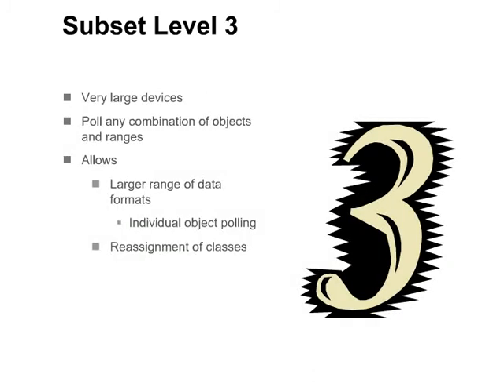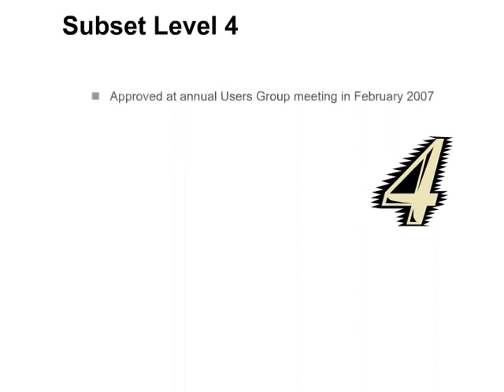Subset level 3 is designed for very large devices. In subset level 3, the master can poll for any combination of objects and ranges. It allows for a larger combination of data formats and also allows for reassignment of classes. Subset level 4 was approved at the annual users group meeting in February 2007. It adds several new features, including an XML version of the device profile document. A level 4 device must provide an XML version of the device profile document containing both the capabilities of the device and its current settings. This file may be obtained by a means other than DNP file transfer — for example, it could be generated by a PC-based configuration software and delivered via CD-ROM or USB mass storage device.